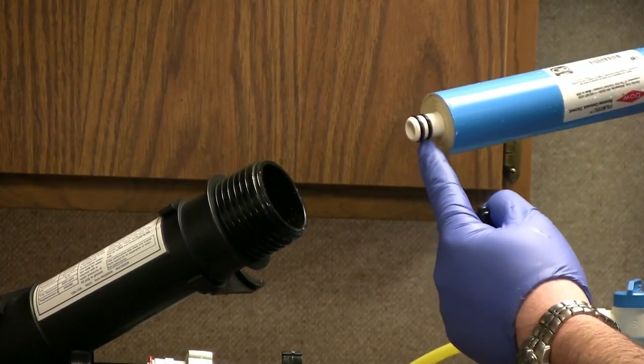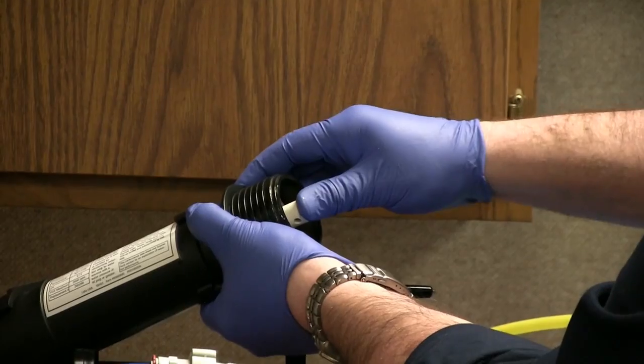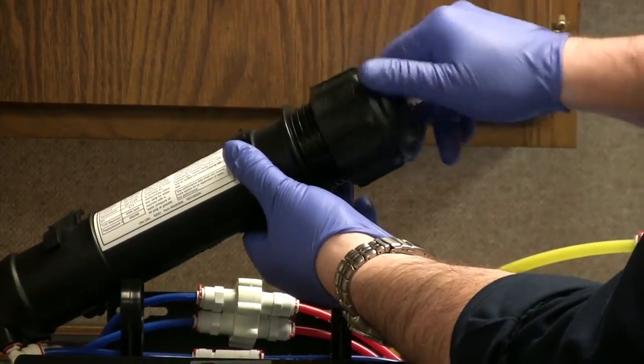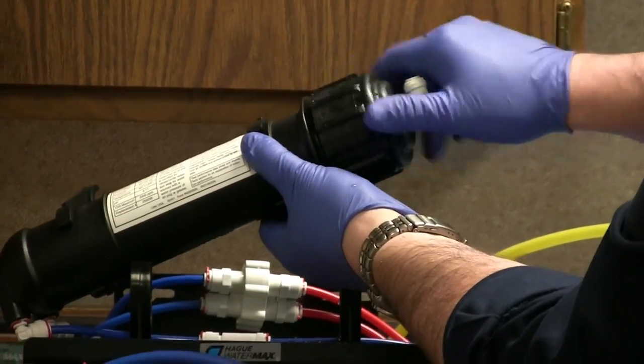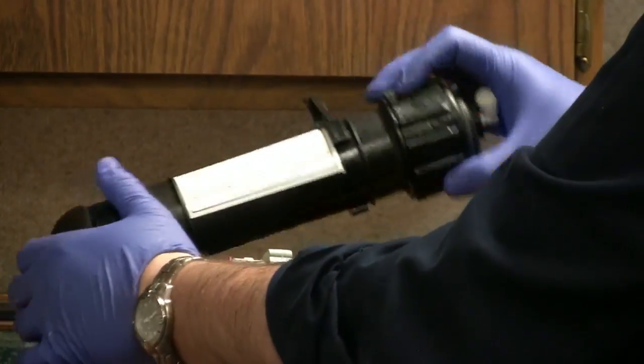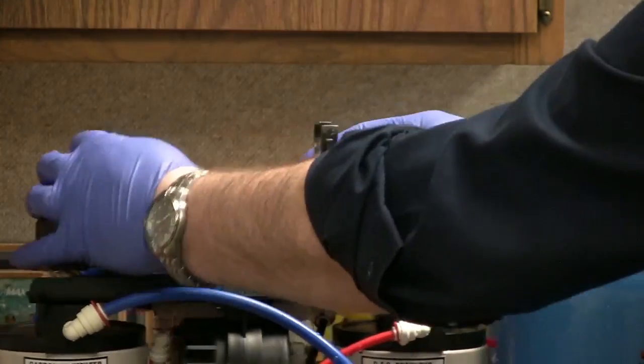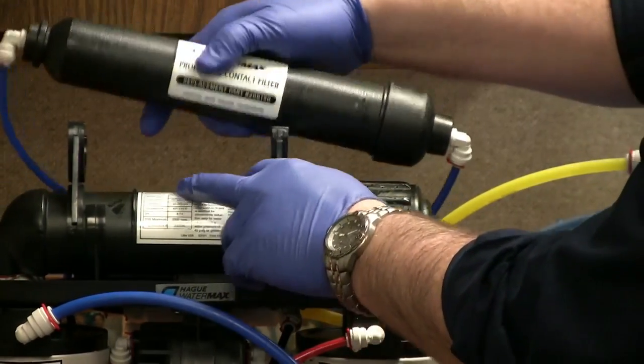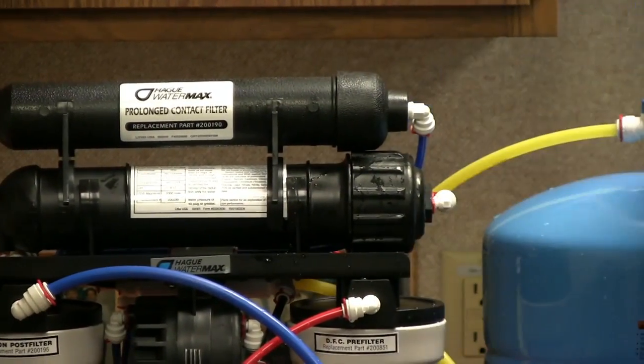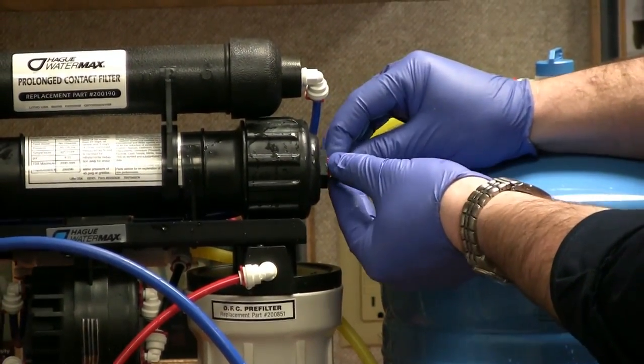Reinsert the new membrane with the double o-rings going in first. Once the membrane is seated, reinstall the cap. And this just needs to be hand tight. Put the membrane housing back in place, the prolonged contact filter, reconnect your feed line, and the small red retaining clip.